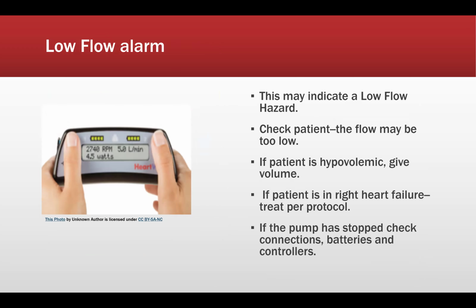Low flow alarm. This is one of the most common ones that we see. This is the control unit that we will see. This may indicate a low flow hazard. Check the patient. Flow may be too low, which typically means the patient may be hypovolemic. If the patient is hypovolemic, give volume, and coordinate how much volume to give with the VAD coordinator and your physician. If the patient is in right heart failure, treat per protocol. If the pump is stopped, check connections, batteries, and the controller.